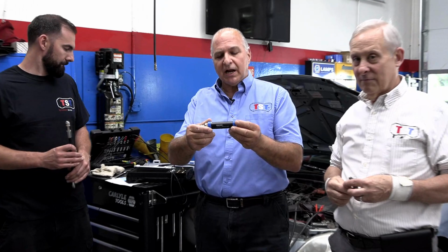In case you're trying to use your compression gauge hoses, you have a Schrader valve in the end. These cannot have a Schrader valve in the end. So if you're going to use a hose with a different fitting, you need to remove that Schrader valve. Here is their pressure transducer setup.